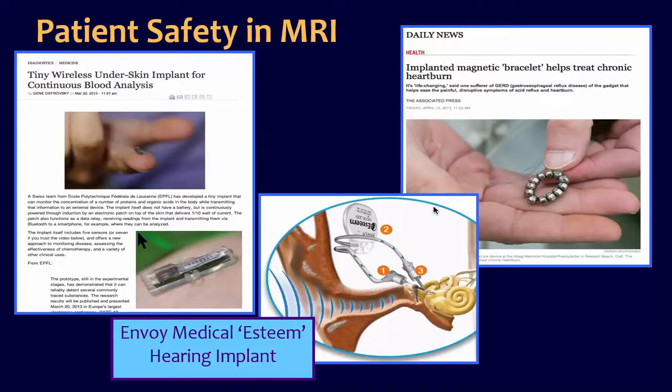And there are still lots of devices that are fairly new and recently developed, but they cannot go into a magnet. So we can't just assume. I know we see things like the pacemakers, and it's great that people are trying to make these conditional so we can scan patients with them. But you've got to be aware that just because it's a new device doesn't mean they've taken into consideration that their patients will have to go into an MR someday. So you just have to remind yourself of that and make sure that you ask lots of questions of your patient, and you make no assumptions.